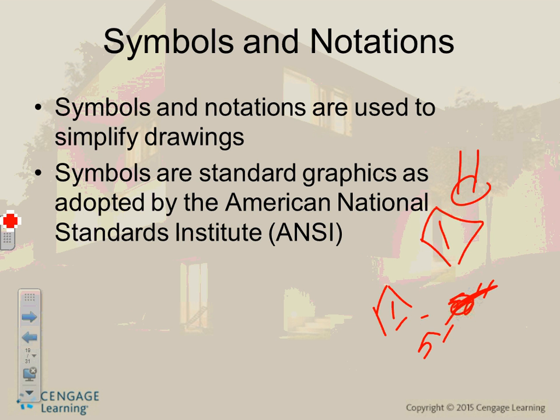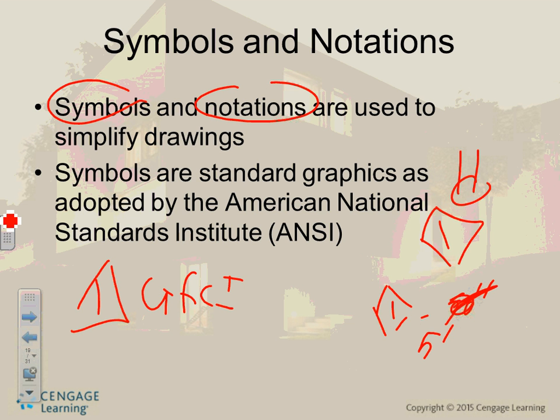They call them first the symbol, then the notations. The notation on the drawing can be a keynote like this, or a general note. A general note, guys, would say right in here - general note number one: all receptacles shall be GFCI. That's your general note. A keynote is when you put a number right next to the symbol to indicate that the height of this receptacle is going to be 5 feet.